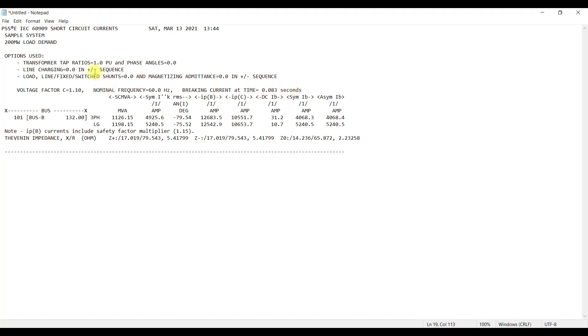Let us discuss the results. The heading shows what type of short circuit analysis was performed and all the options used. The voltage factor C is 1.1 because I selected maximum fault current. The system frequency is 60 Hz. The contact breaking time is also shown. If you change the contact breaking time you will see changes in the asymmetrical current and the DC current. With a shorter contact breaking time, the DC current has not subdued yet and remains higher, which increases the asymmetrical current. The longer the time you consider, the lower the asymmetrical value; the shorter the time, the higher the value.